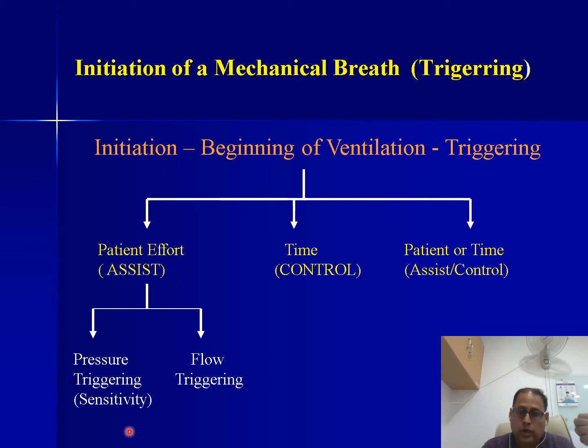The other is the flow triggered breath, where again when the patient pulls in air, there is a fall in flow. The machine senses this through a sensor present within the machine, which you can set the sensitivity levels for, and it is a flow triggered breath.